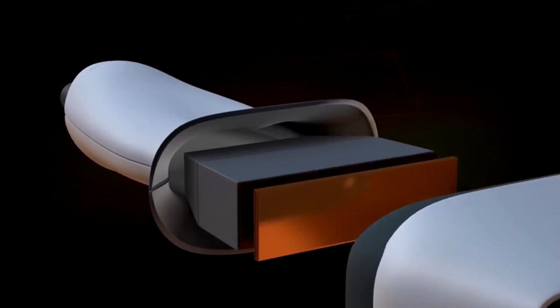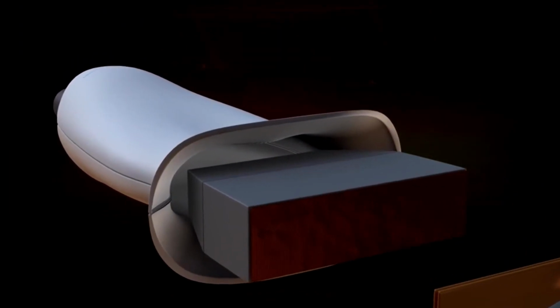Now applying this to ultrasounds, the transducer actually consists of a large array of these piezoelectric crystals. And since it has a source of electrical energy, the crystals can now produce high-frequency waves. To be a little more specific, only every other crystal is hit with electrical energy, so that when the ultrasound waves are reflected back, the other crystals can transform these sound waves back into electrical energy.